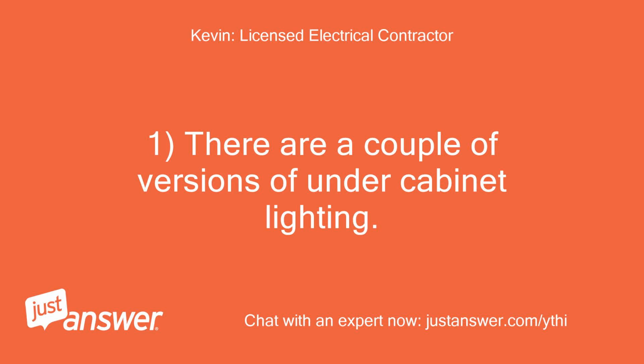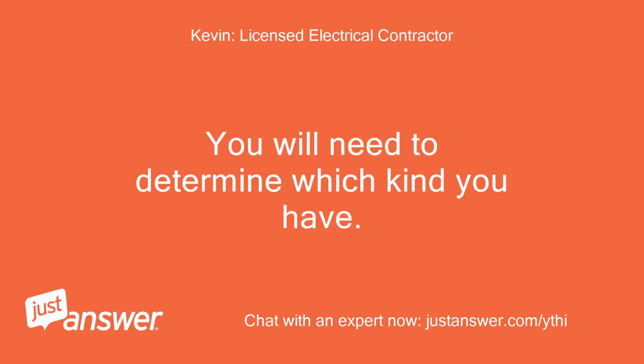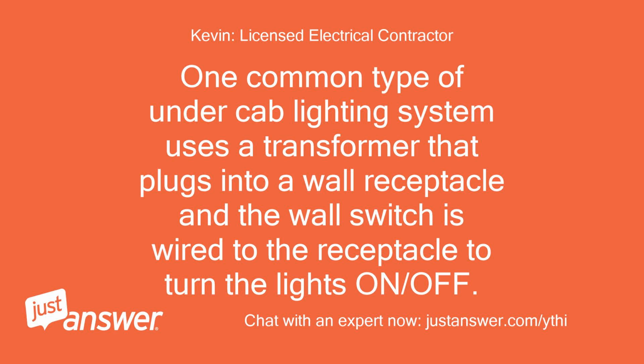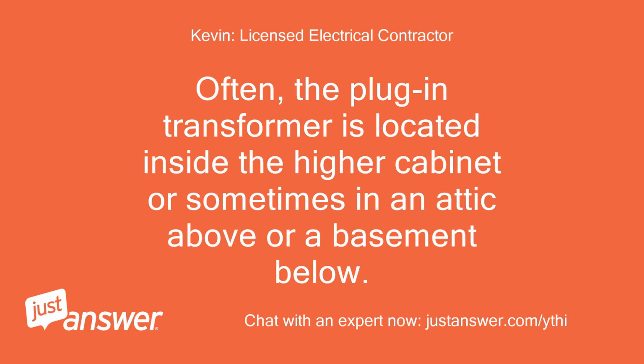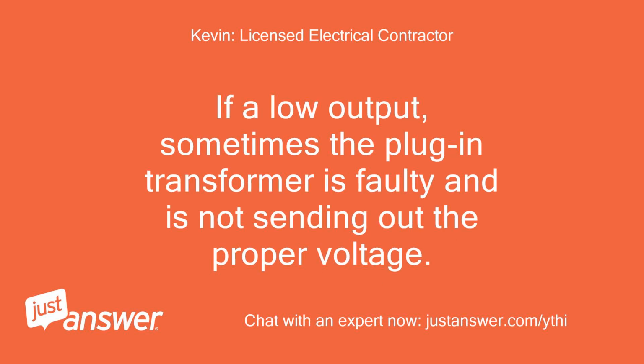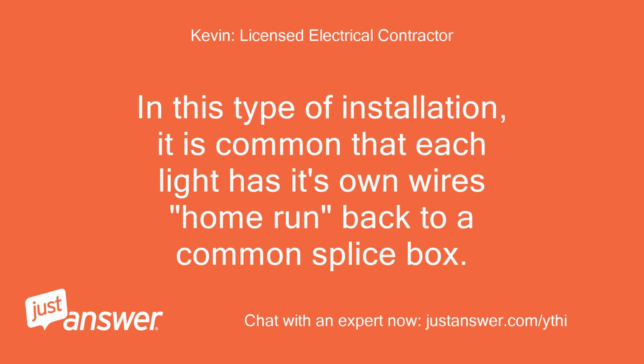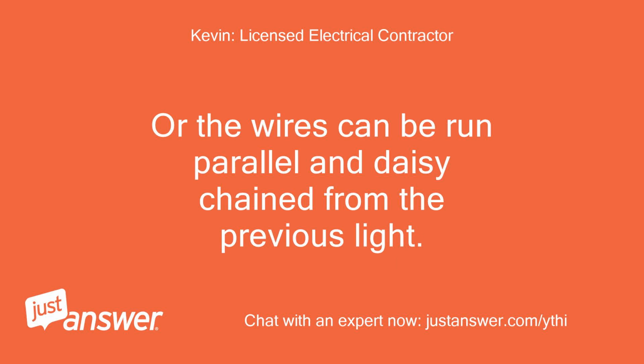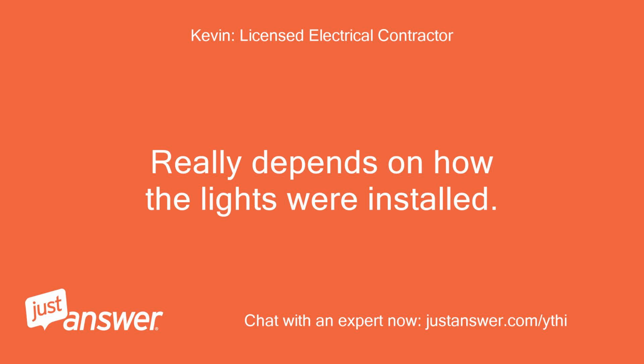1. There are a couple of versions of under-cabinet lighting. You will need to determine which kind you have. One common type of under-cab lighting system uses a transformer that plugs into a wall receptacle and the wall switch is wired to the receptacle to turn the lights on/off. Often, the plug-in transformer is located inside the higher cabinet or sometimes in an attic above or a basement below. If low output, sometimes the plug-in transformer is faulty and is not sending out the proper voltage. In this type of installation, it is common that each light has its own wires home run back to a common splice box. Or the wires can be run parallel and daisy-chained from the previous light. Really depends on how the lights were installed.